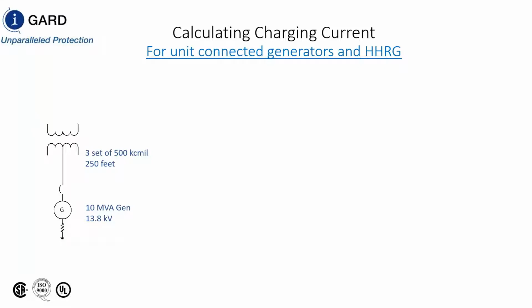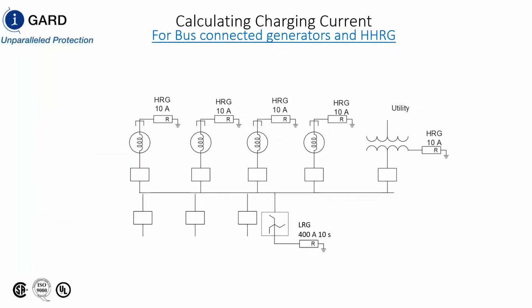So we're going to try to calculate what the charging current is. And I've shown an example here of a unit connected generator. The difference between a bus connected generator and a unit connected generator is that the unit connected generator is connected to a step-up transformer, and then it's distributed here. With this particular system, all you have to do with the resistor here is overcome the charging current. If you had a bus connected generator like this one, you only need to size this resistor for this portion of the circuit to overcome the charging current in this area. Once this breaker is closed, the 400 amp 10 second resistor will have enough resistive current to overcome the charging current.